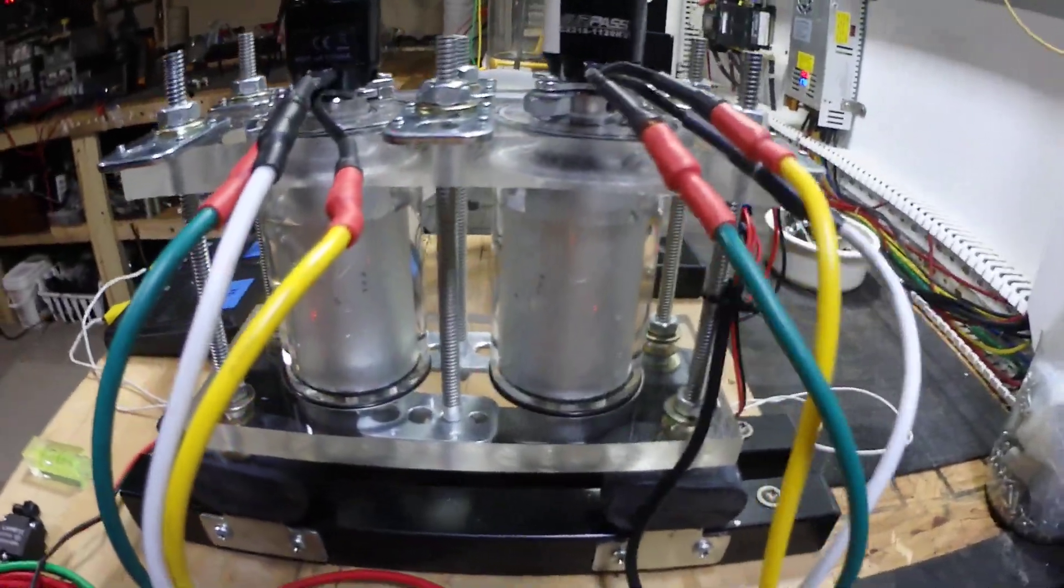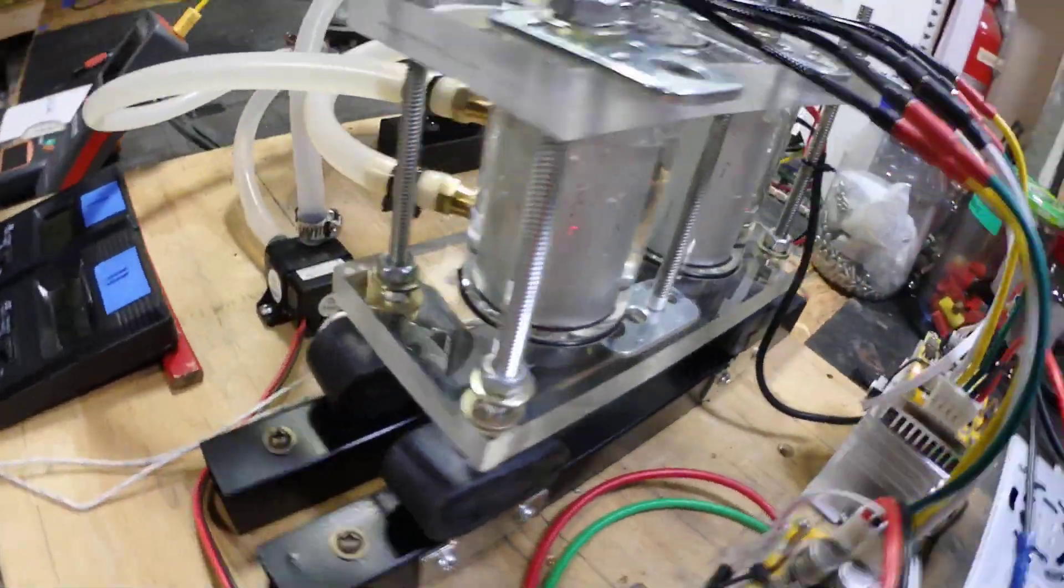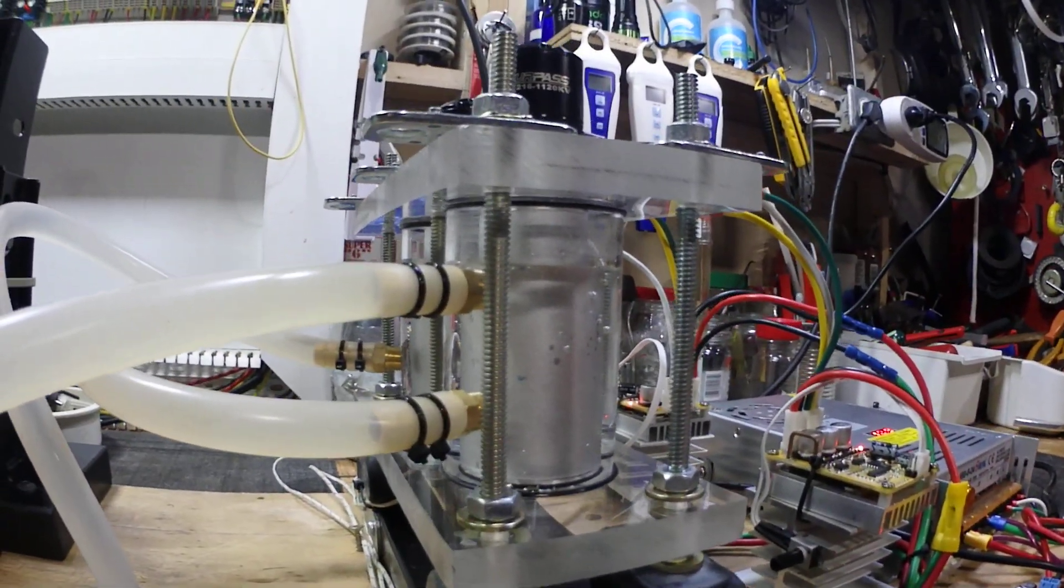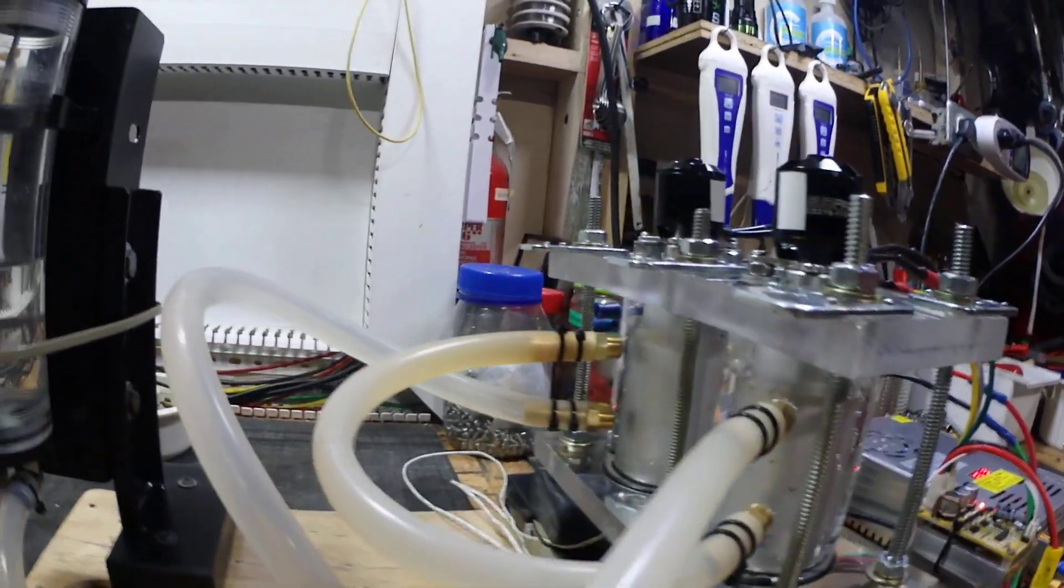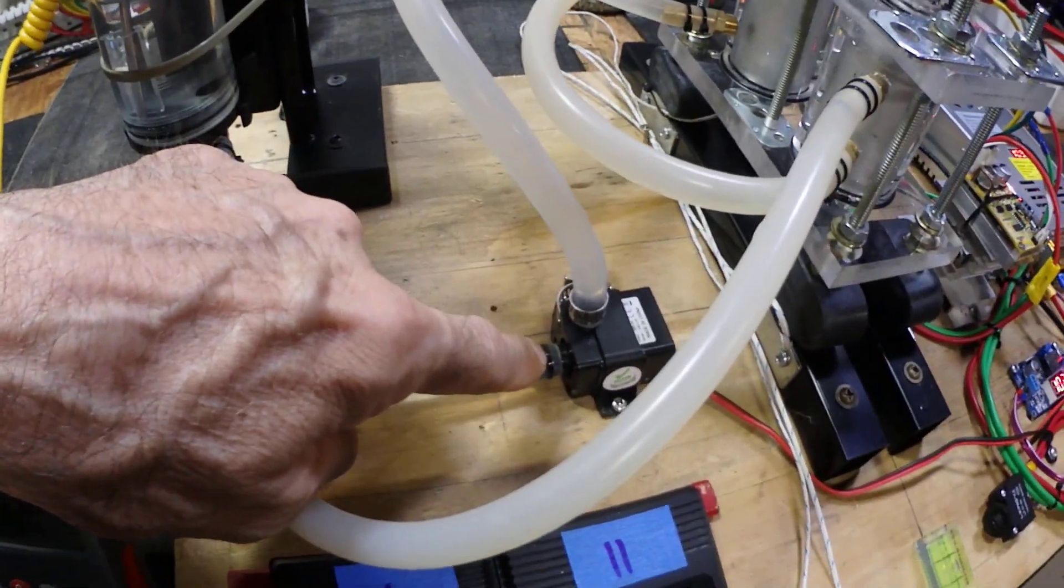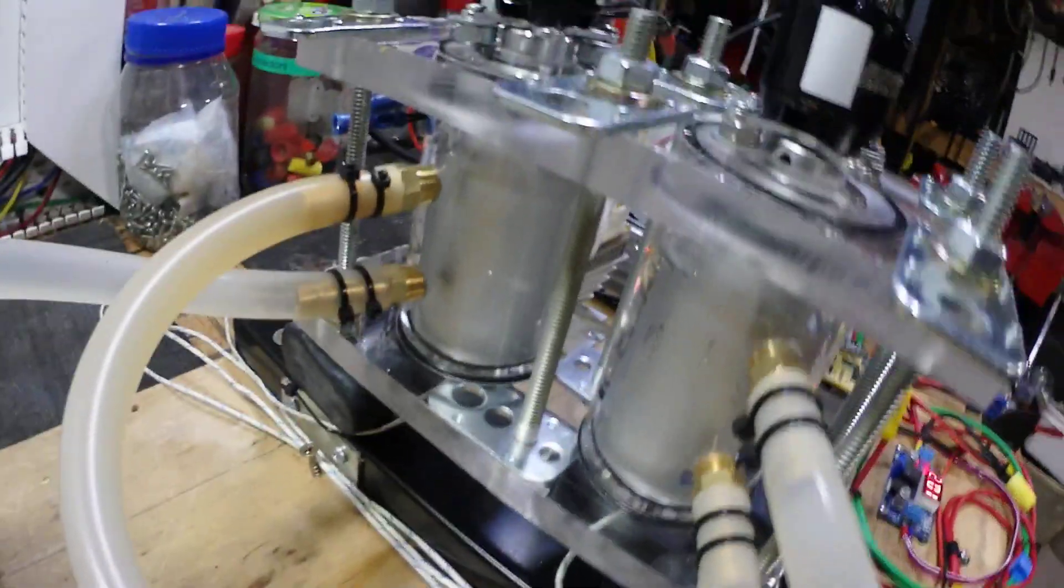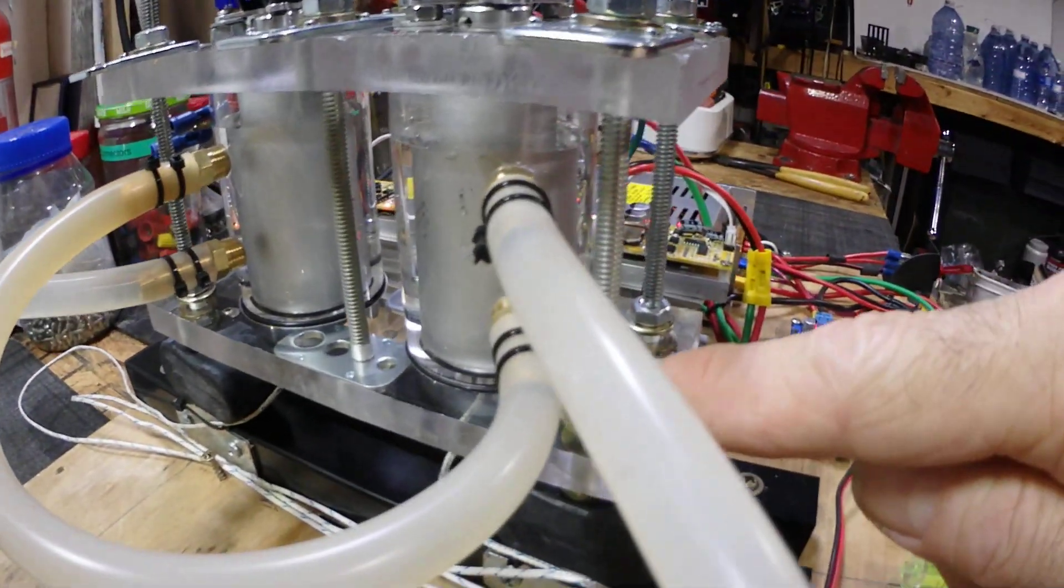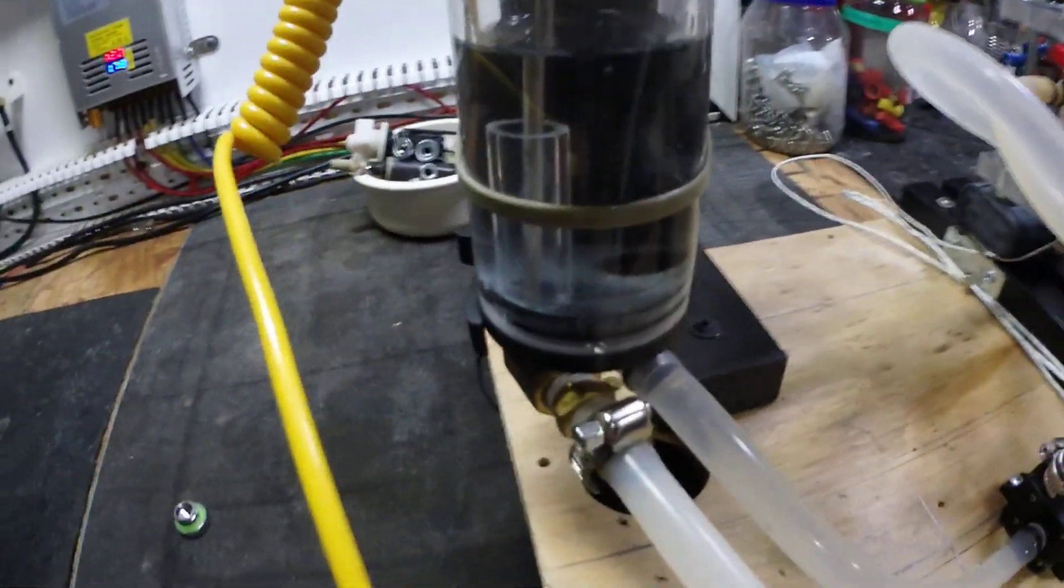If you can see that, there are my water jackets. Let's see the water level there. The first stage, like I said, will come out of the reservoir right into the pump, into the bottom of the first stage, out of the top of the first stage, into the bottom of the second stage, out of the second stage, back into the reservoir, and that's where the temp probe is.